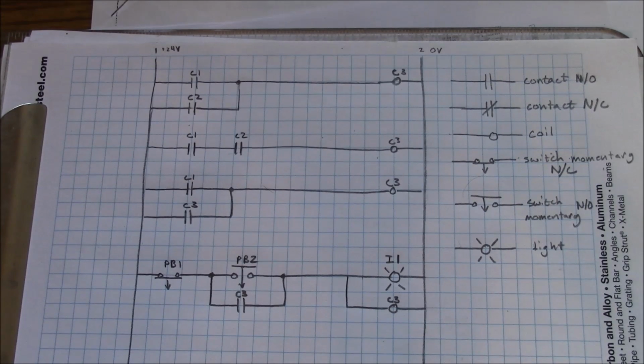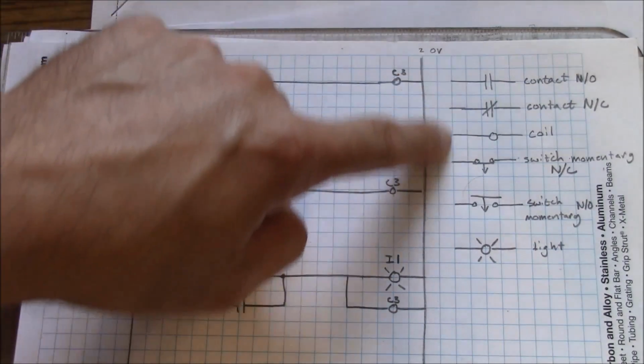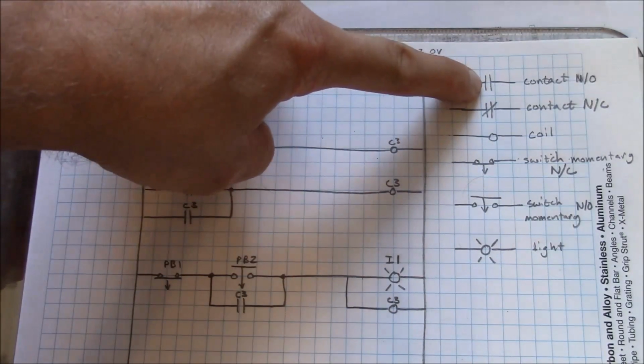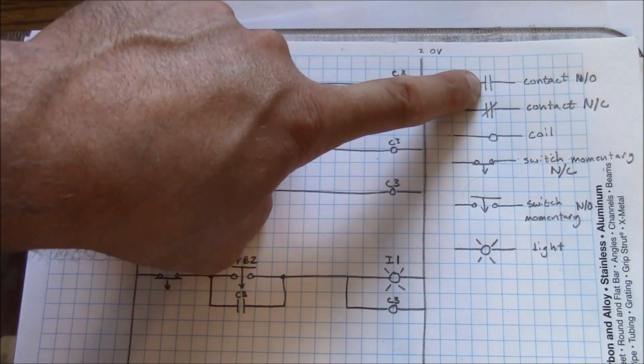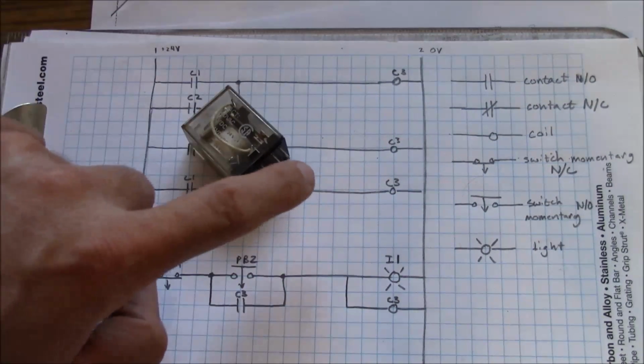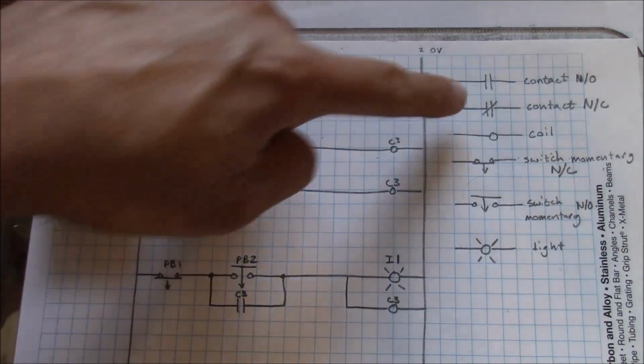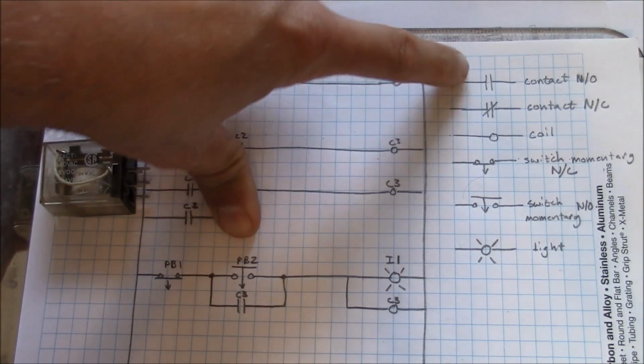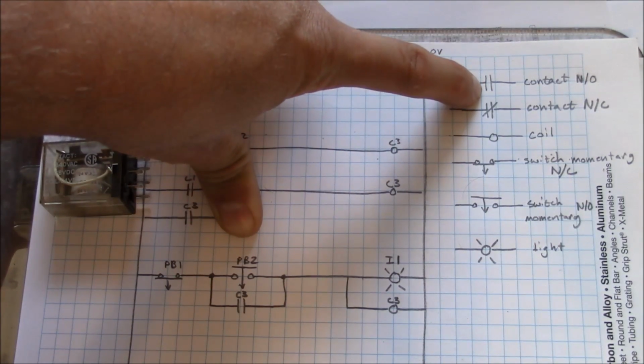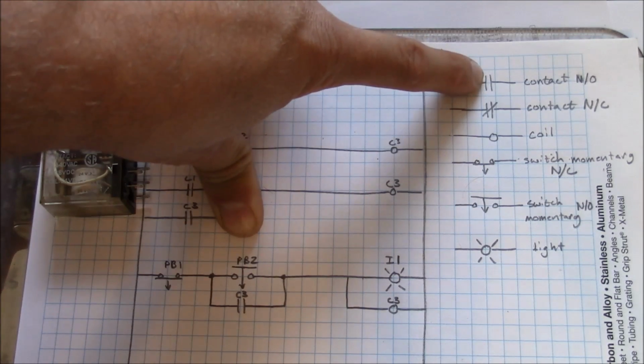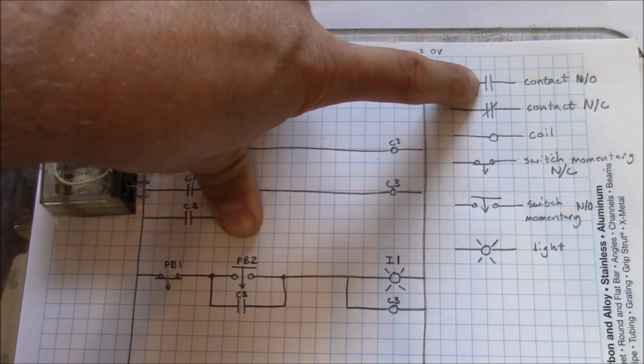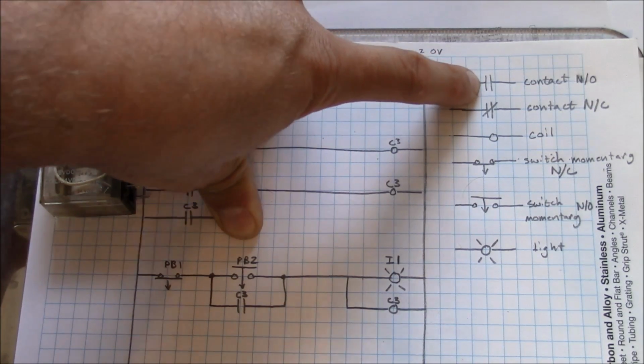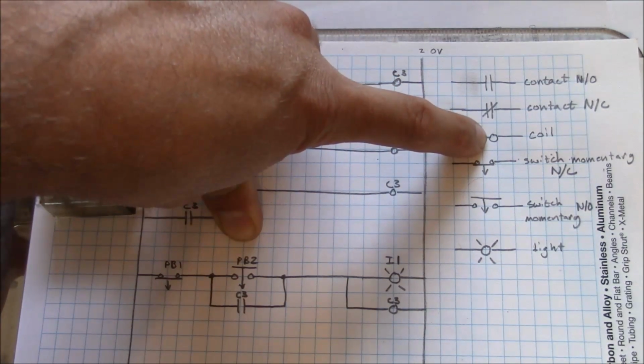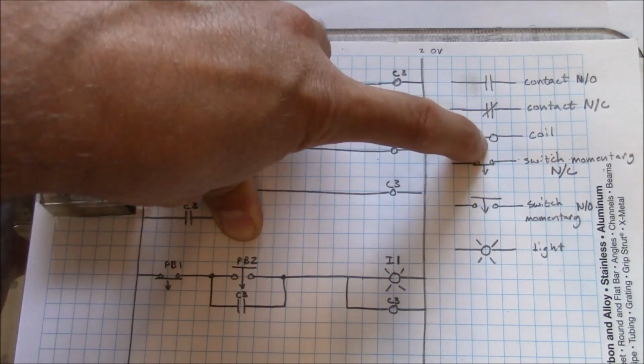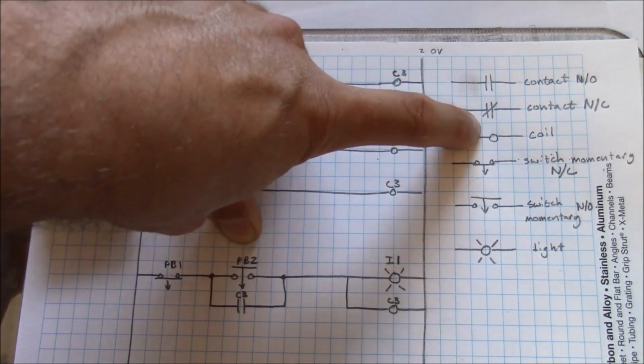Okay, so this is a really rudimentary drawing of some logic, and over on this side here I've drawn out what the various symbols mean. These bars here represent a contact that's normally open, and that's a contact on the relay. So that's this side of the relay. This represents a contact that's normally closed. This symbol here would normally represent a capacitor, like on an RC circuit drawing or a circuit board drawing. But in the ladder logic system, they typically use this symbol for a contact, basically a switch. And then a round circle like this typically indicates a coil. Sometimes it's drawn as a box, and I think the Mori Seiki drawings are that way. I'll show you that in a minute.